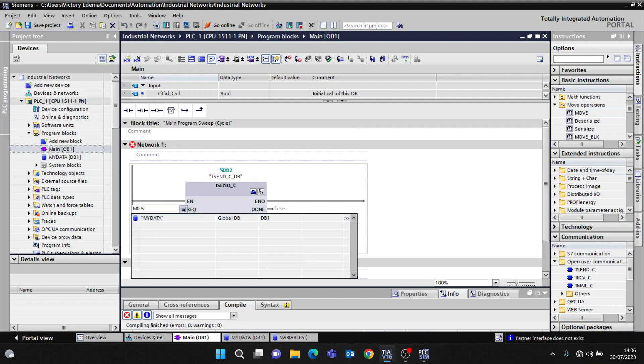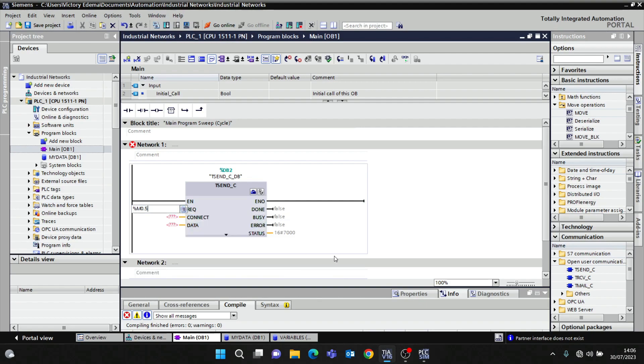You must configure T-Send and T-Receive in both PLCs. For PLC1 we'll configure T-Send, and for the other PLC we'll configure T-Receive. I'm going to use a clock so it works on a rising edge — a one-second clock.